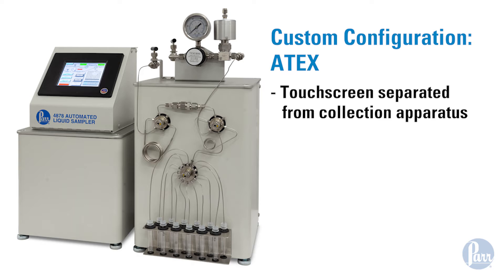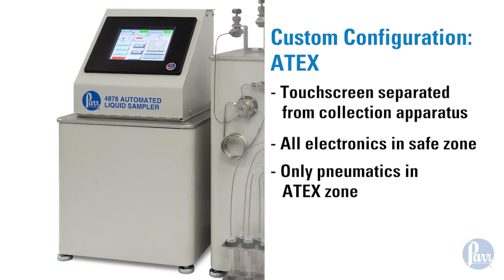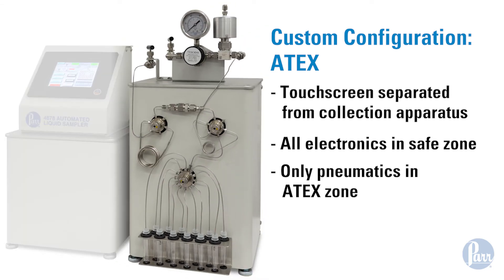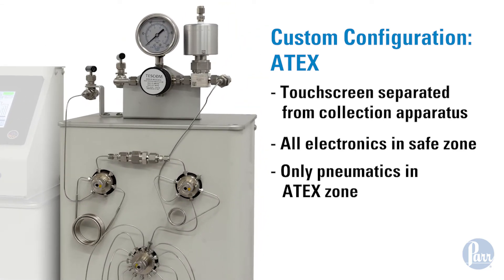This variation separates the sample collection apparatus from the control electronics to allow sampling in an ATEX environment. Pneumatically actuated valves allow the sampling apparatus to be placed in the ATEX zone while the control system is remotely located.